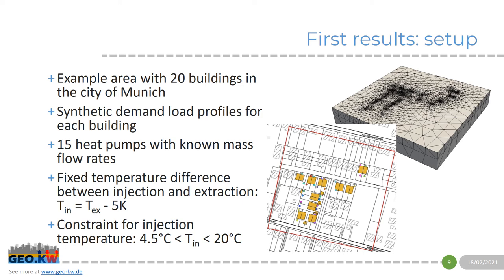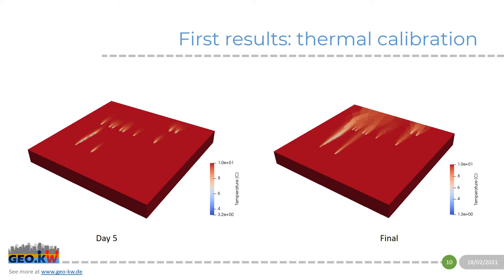We then ran first the thermal calibration, the initial PFLOTRAN simulation for all of the heat pumps. You can see the results of the thermal calibration here. On the left there is the result of the 5 days and then on the right the final result, the whole time horizon. You can see all the 15 heat pumps and there are still really low values. It goes down to 1.5 degrees Celsius, which shouldn't be the case. But so far we did not apply the optimization, so there are no constraints yet.